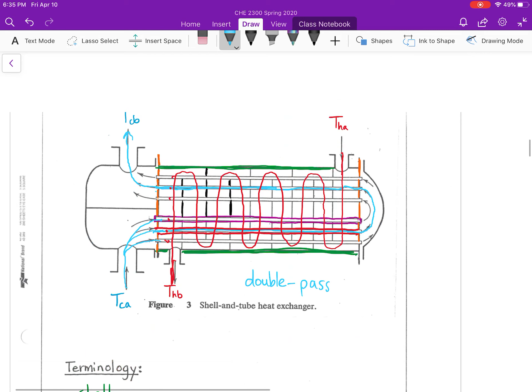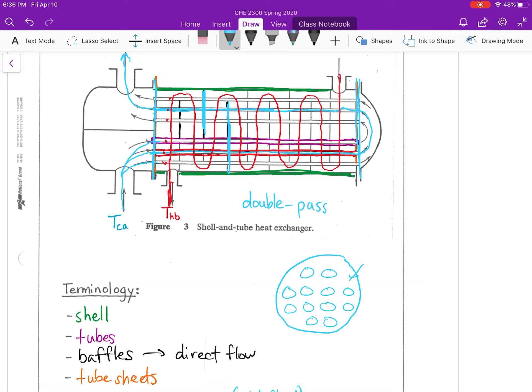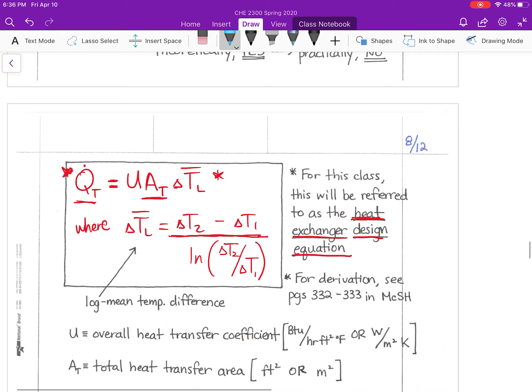My tube sheets define what type of pattern I have, and they already have holes cut in them, meaning I cannot add more tubes than that to this heat exchanger. If I wanted to, I would need to change the tube sheet on both sides, and I would more than likely also have to change the baffles. So expanding a shell and tube heat exchanger is not straightforward at all.